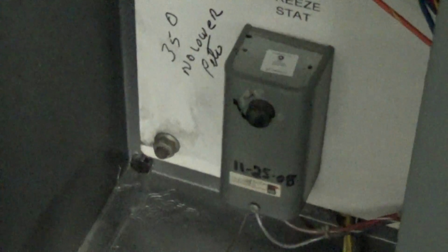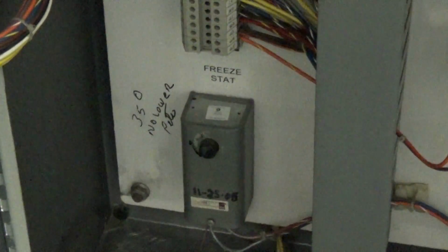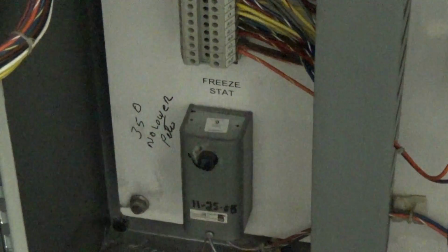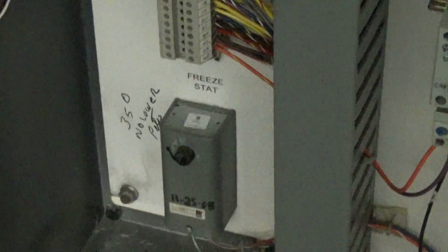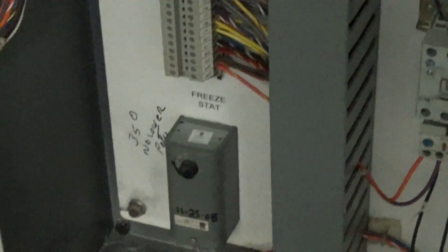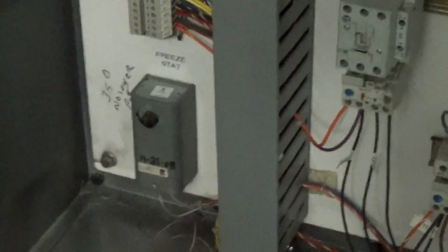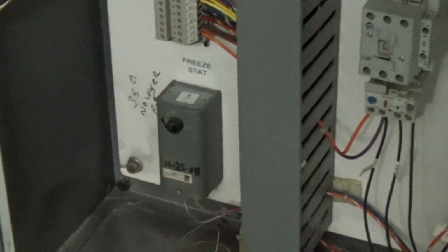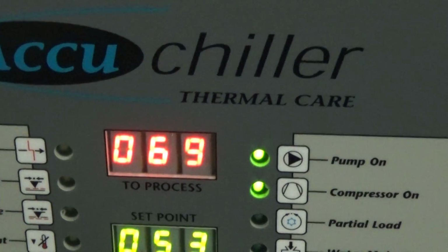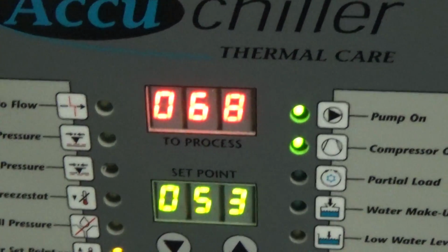So, we have a freeze stat here. That freeze stat is tied into the fluid line right next to the heat exchanger, and that's set at 35 Fahrenheit. And that's just for protection. If somebody sets this dangerously low, that's going to turn the chiller off, because you don't want to get below that temperature. So now we have 2 compressors going. It's actually chilling pretty well.